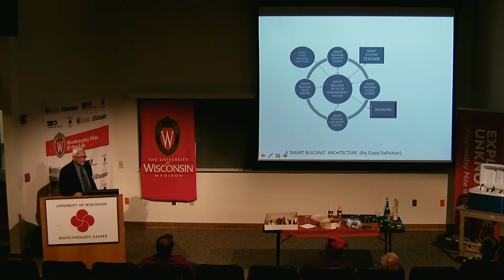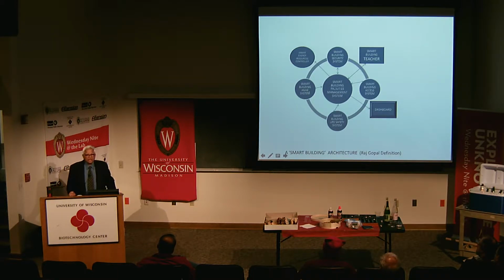Now, if you take the smart building HVAC system, when I say a system is resilient and self-healing, take a cooling coil. If the valve in the cooling coil supplying chilled water to the cooling coil, instead of going to the full open position, gets stuck at 50%, a resilient system having end-to-end resiliency will send a signal to the chiller to reduce the temperature of the chilled water supply so the capacity of the cooling coil can be increased. So this is an example of resiliency and self-healing.